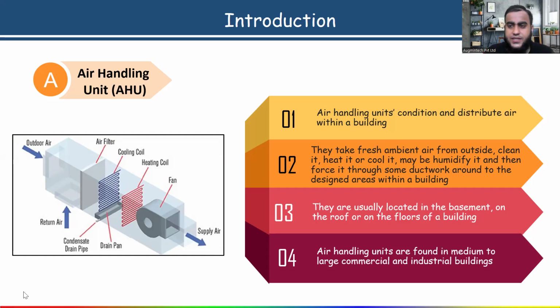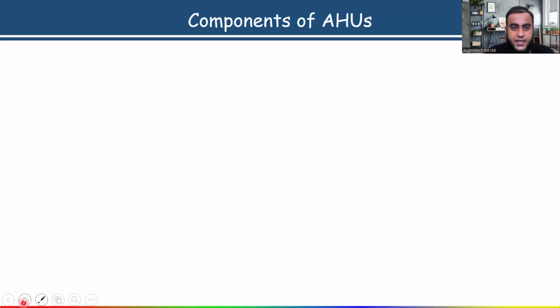Okay. So now we'll discuss, just in short, the main components of the AHU. You can see in this figure also it is given. Here I have taken one schematic drawing of an AHU in this image. You can see the different components shown. Can you see the supply air fan, heating coil, cooling coil, even the air filter, different types of filters we are using. Humidifier, dehumidifier is optional. And outdoor air we are taking from the back side. Return air from the bottom. And from here we are supplying the conditioned air to each and every room via ductwork. So all the components we have to discuss in short. Then we start the sizing and selection.